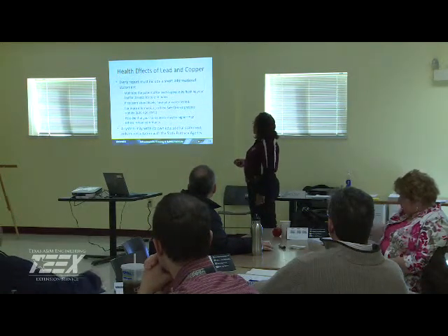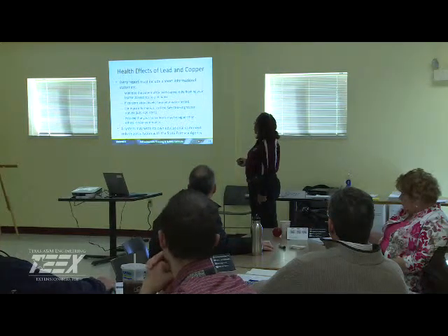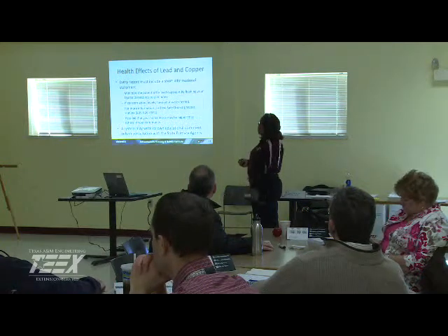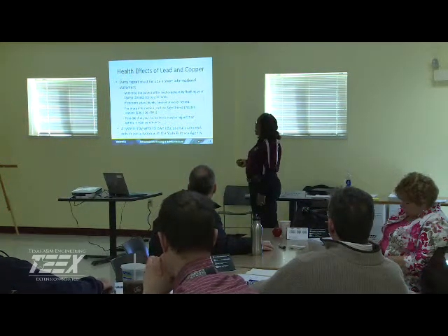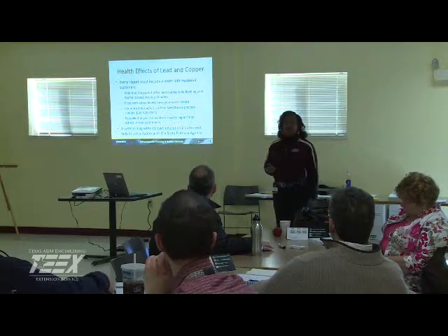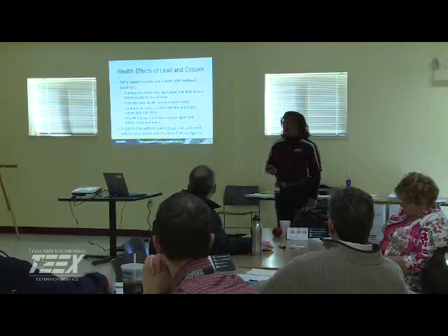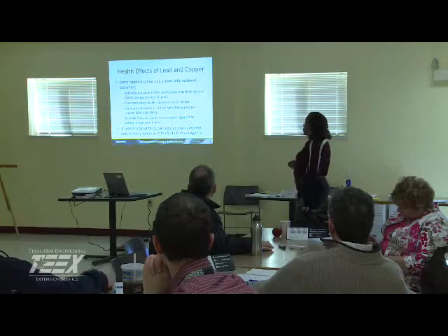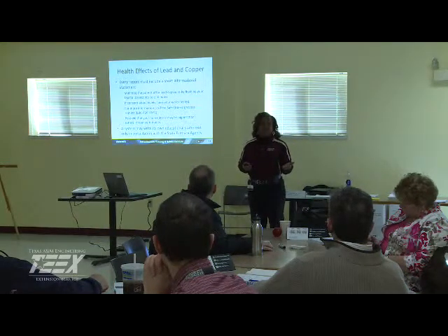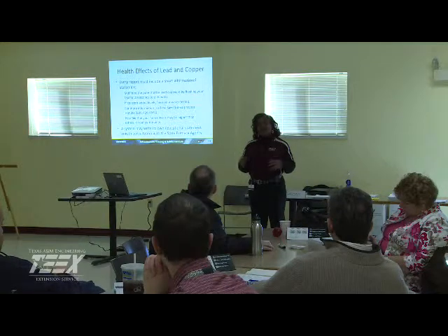All right, now for some of the informational statements, and also to help the customer react to it, you want to educate them. Simply tell them to allow their water to run before using it, 30 seconds to 2 minutes. A rule of thumb is to wait till there's a temperature change, because the lead and copper is leaching into the water because of stagnant water.